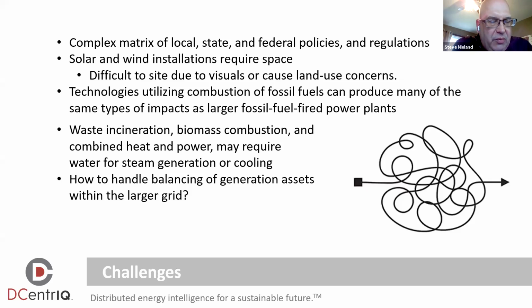One of the things we do with larger energy systems is work with utilities and run impact studies, because we have to know if we're not able to consume everything on site. For instance, let's say we put in a large 2 or 3 megawatt system for a manufacturing plant, and the plant only runs 5 days a week. What happens to that energy on Saturday and Sunday? Can the utility take it? If they can, how far upstream—can they take it on the branch that installation is on, or do they have to take it back beyond their substation into their wider network? So we need impact studies on how we can handle and mitigate that before we're able to build the installation.